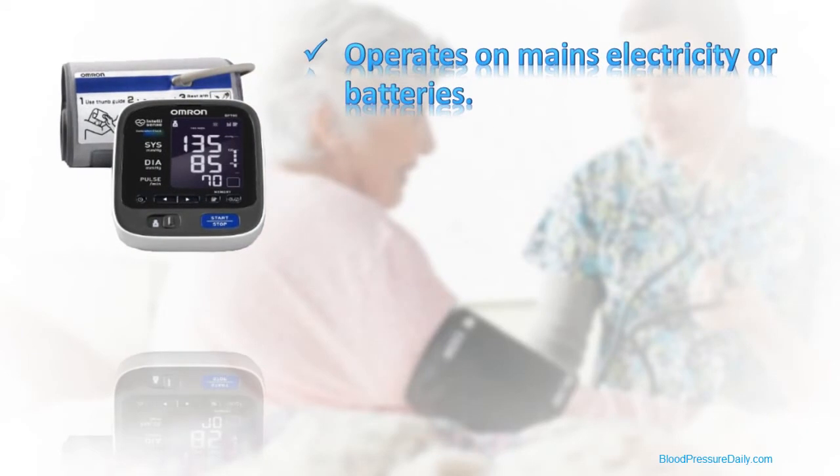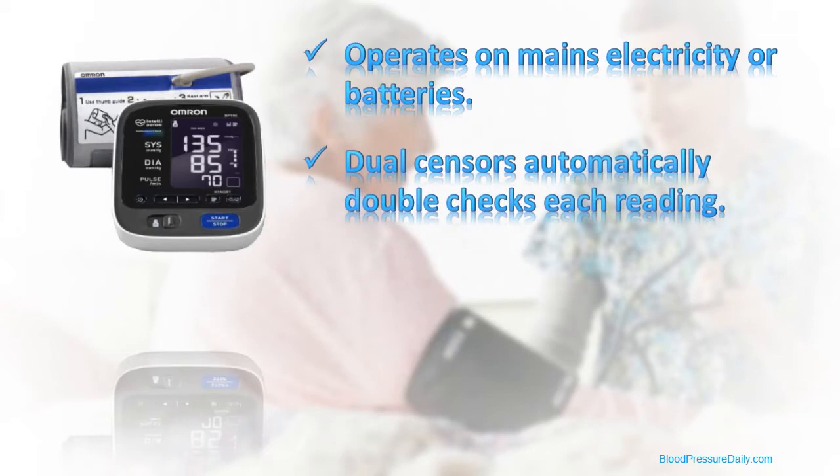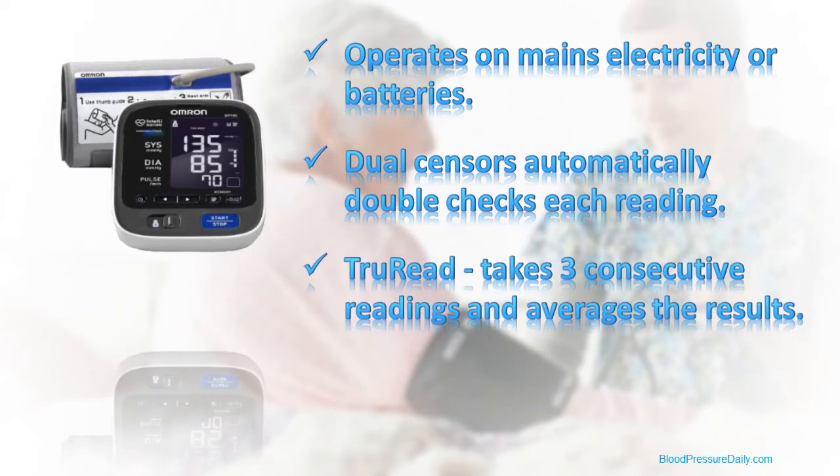Two further advanced features seen on Omron's 10-series monitors are dual sensors, which automatically double-check every reading to ensure the highest level of accuracy, and TruRead, which allows you to take three consecutive readings one minute apart and display the average of these readings. This facility was introduced to meet the latest international guidelines for measuring blood pressure.